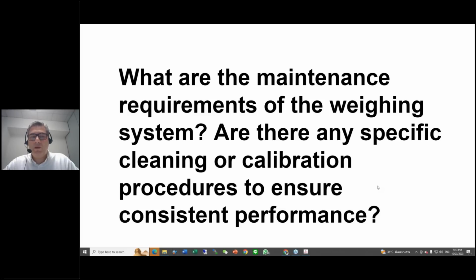Every month or 6 months, something more is required, but really no big effort is needed from the maintenance team. Also for the calibration procedure, it depends. We have customers that run calibration every week, and customers that run it every 6 months. Because calibrating all the scales, especially in a complex machine with more than 50 scale load cells, requires hours.